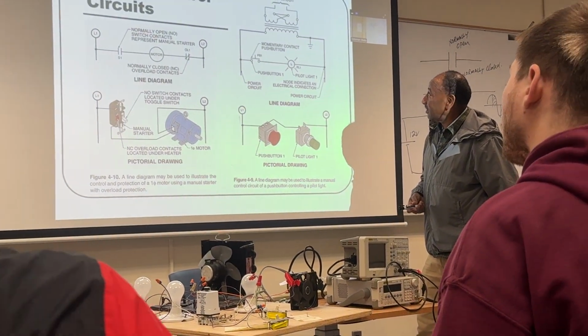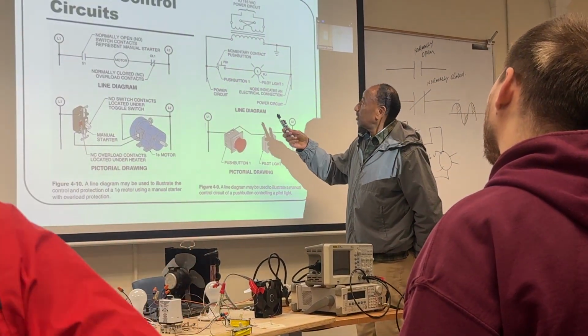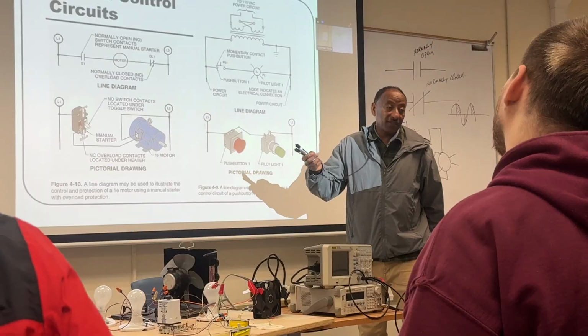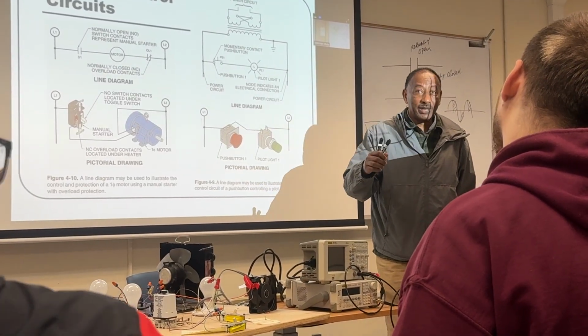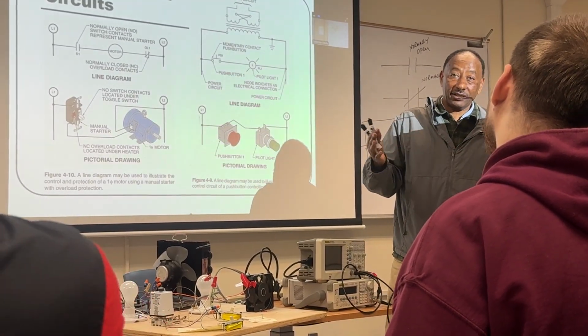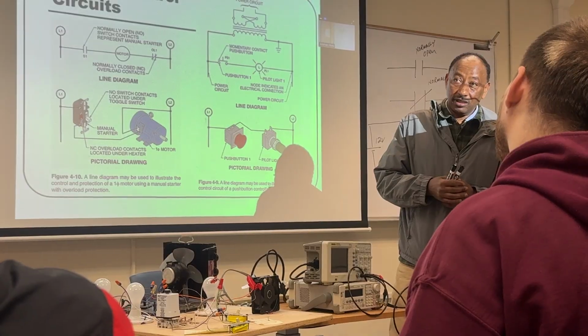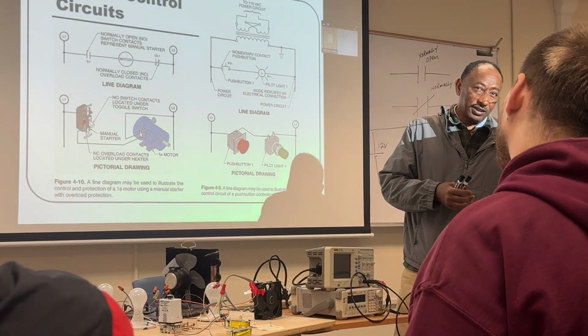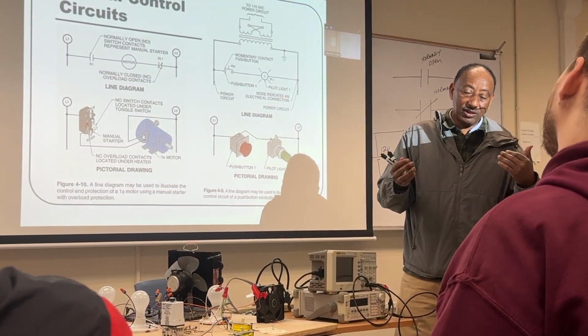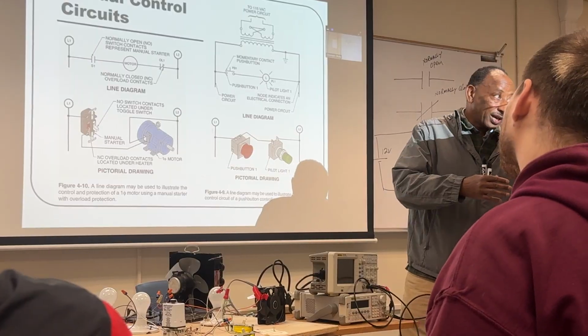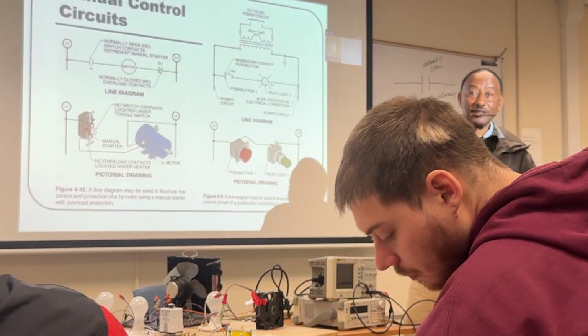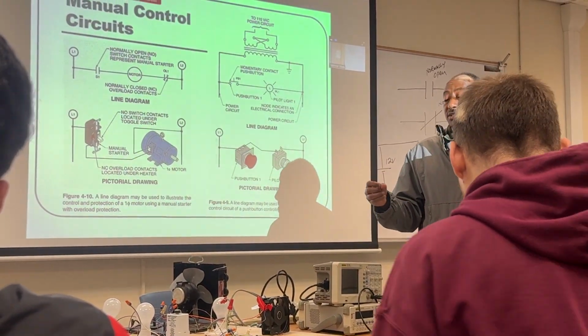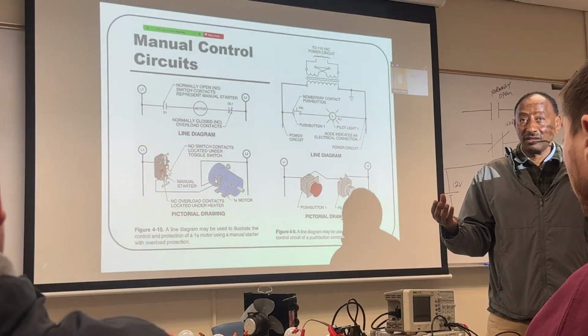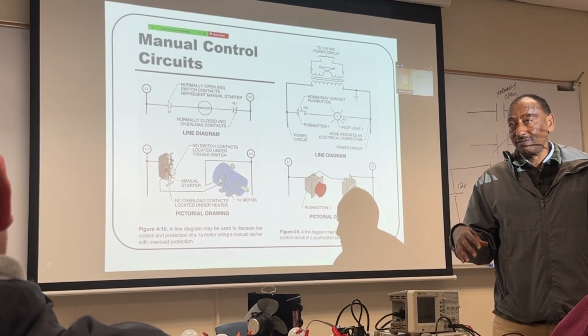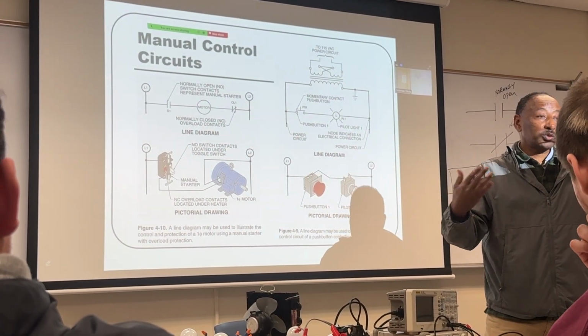A different line diagram. Usually with relays, you only take a few voltages. The relays are basically a conduit to connect something. For a relay, or if you have a solenoid too, they need only a very small voltage. Some relays you only need 9 volts, or some may even need 5, but they can connect 120 volts.